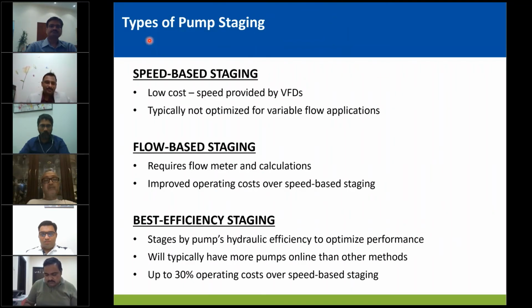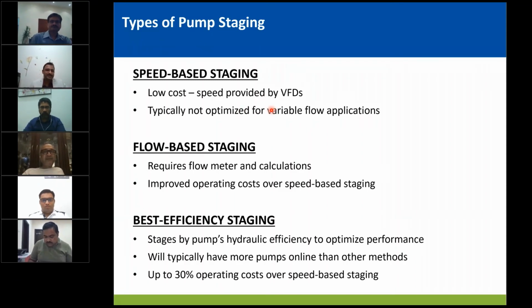So, type of pump staging. Now, speed-based staging is very common today. 98%. It's popular in the region. There is a BMS controls contractor or plant manager that takes staging controls of the pumps. And once the first pump is loaded to, let's say, 90%, it starts the second pump.